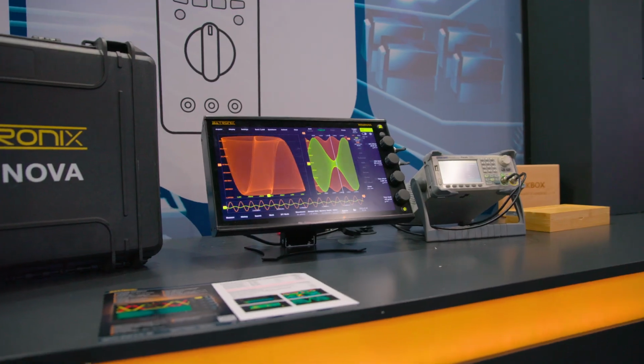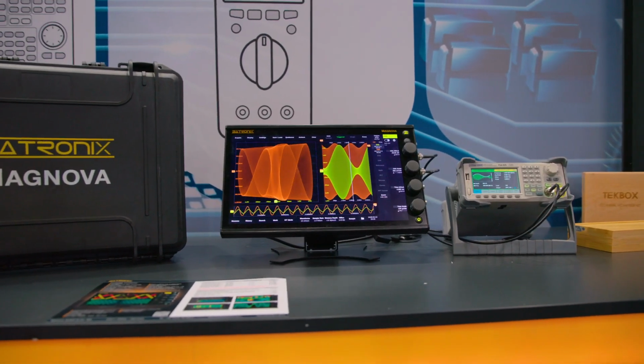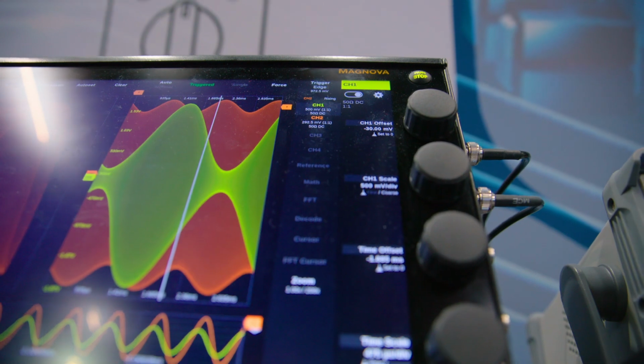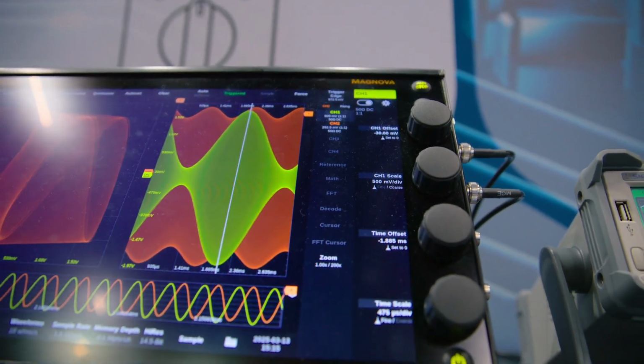This high performance of the new oscilloscopes is only possible when all these features are built into the FPGA, the programmable hardware. The processor can't analyze so many data in a short time. The FPGA can parallelize it and analyze a lot of data in parallel, and that brings up the performance a lot. Otherwise, if you want to use all channels at the same time, then you go to 25 gigasamples per channel, for instance. So that's the compromise. Of course, that depends on the model that you choose.